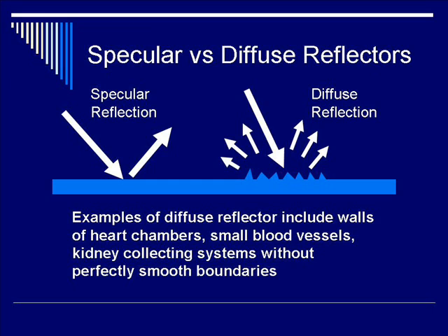Note that even though diffuse reflectors have very weak echo signals, in general the image quality is insensitive to the orientation of the reflector compared to the echo from a smooth specular reflection. Therefore, an example such as the liver will always give a very homogeneous yet speckled picture, regardless of what angle you hold the ultrasound probe against the patient's body.